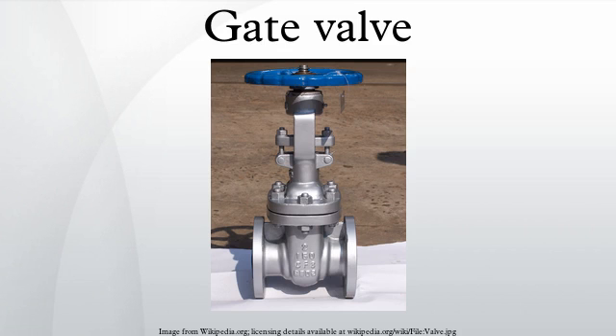The gate faces can form a wedge shape or they can be parallel. Gate valves are primarily used to permit or prevent the flow of liquids, but typical gate valves shouldn't be used for regulating flow, unless they are specifically designed for that purpose. Because of their ability to cut through liquids, gate valves are often used in the petroleum industry.